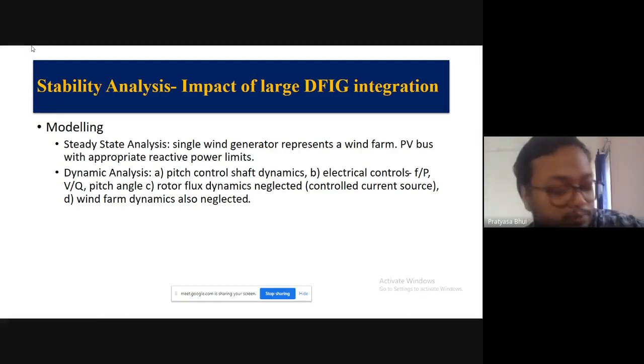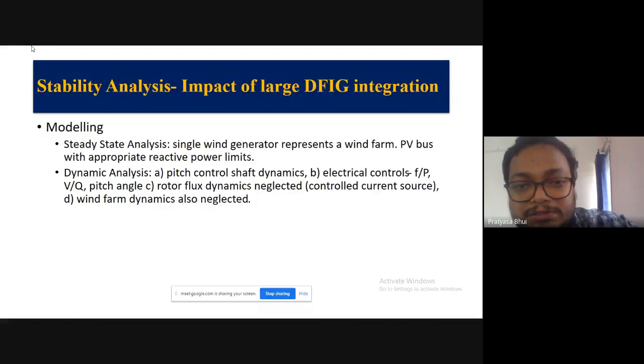So for steady state analysis or load flow, we'll consider the renewable generator as a PV bus with appropriate reactive power limits. Nowadays, all big renewable energy plants are supposed to control the voltage as well, the voltage at that bus. As it is injecting power and is able to control the voltage at that bus, we are considering it as a PV bus with some appropriate reactive power limits.